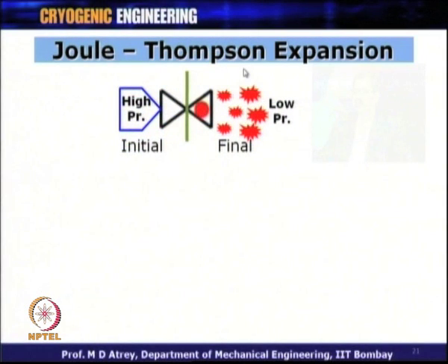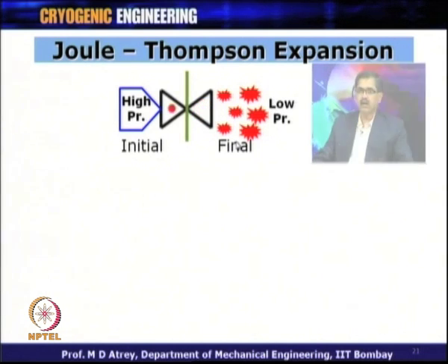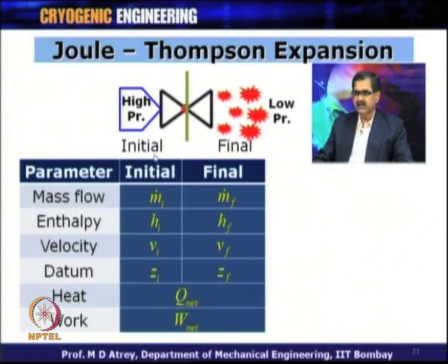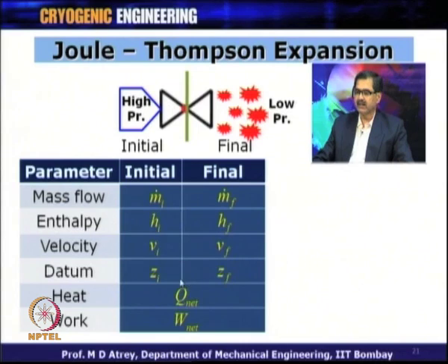Now we come to the very important Joule-Thompson (JT) expansion. Whenever high-pressure gas passes through a constriction — a valve or capillary tube — the gas expands from high pressure to low pressure, which may result in lowering of temperature. The gas enters at a particular pressure and temperature and leaves at lower pressure, with a possibly different temperature. To analyze this, we must compare parameters at the initial and final states: mass flow rate, enthalpy, velocity, and datum level, along with heat and work involved.